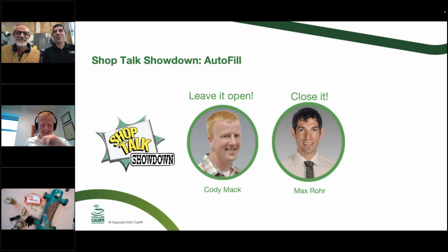So what I would see sometimes, and it's just an absolute heartbreaker for the contractor, the wholesaler, the engineer, everybody involved, the manufacturer, the rep, is if there's an unaddressed air issue, or a leak, hopefully it doesn't freeze and you don't have water filling on top of your art collection or something like that. But if you keep introducing fresh water, it's bringing in more minerals all the time. So if you've got just a drip somewhere that you can't even see, in the slab, in the concrete, you're bringing in more and more minerals and you're filling that boiler up with sand essentially.